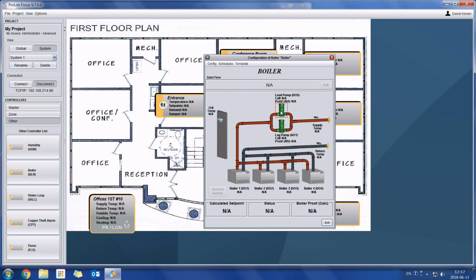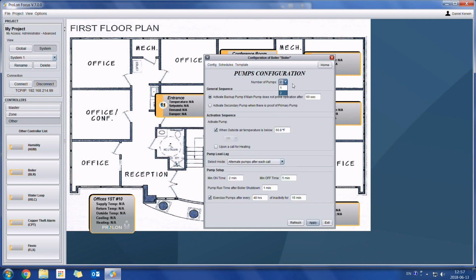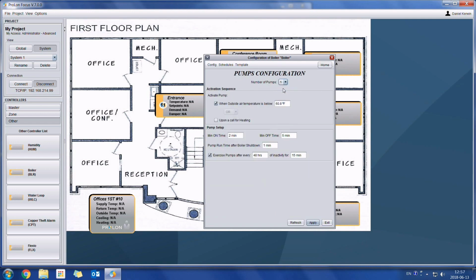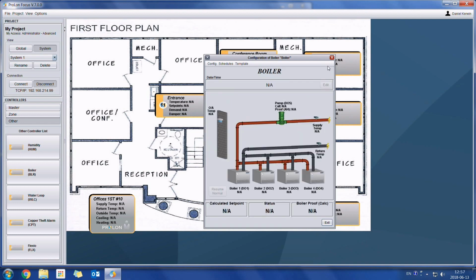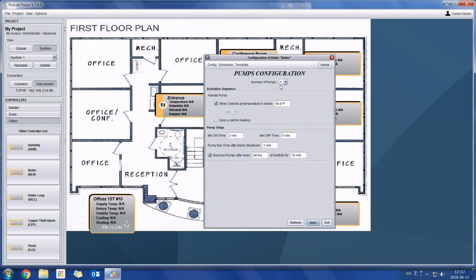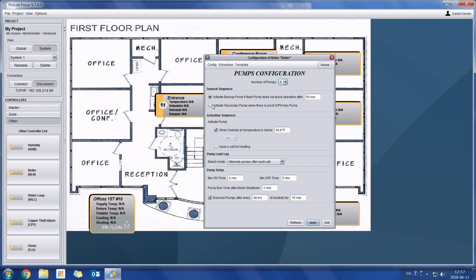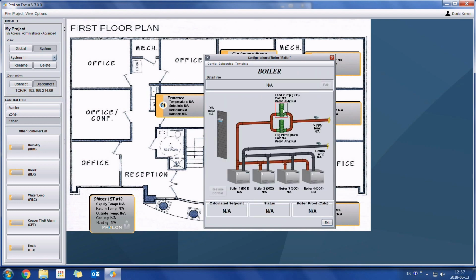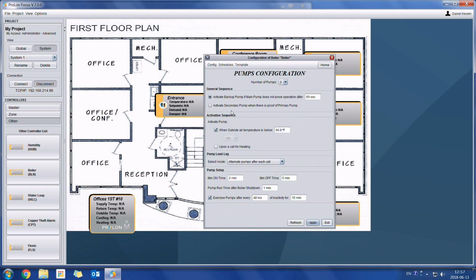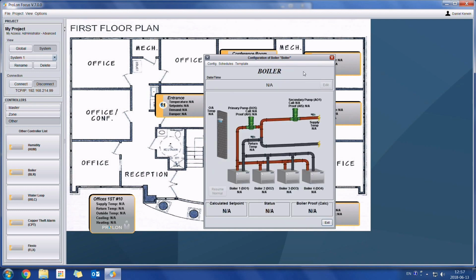If we take a look at the pumps, here we can choose how many pumps we have. Is it 1 or 2 pumps? If we just have 1 pump, then the graphic will automatically change. If we do have 2, we have 2 general sequences. If it's a main pump with a backup pump, then we'll see it as we saw before. Or in case we have pumps on a primary loop and a secondary loop, as we can see, the graphics will change a little bit.